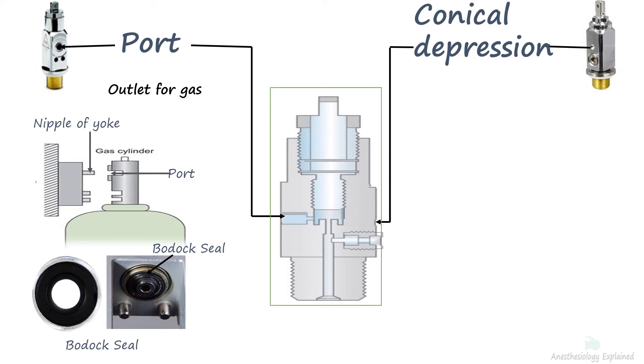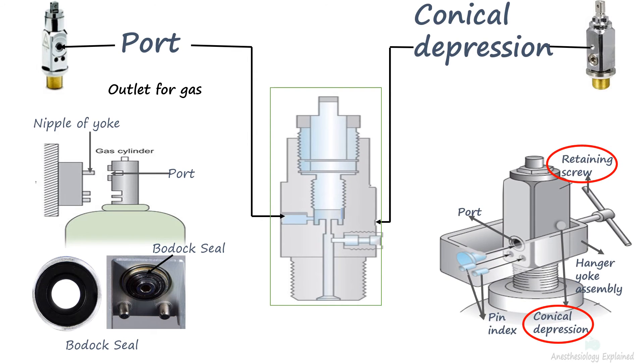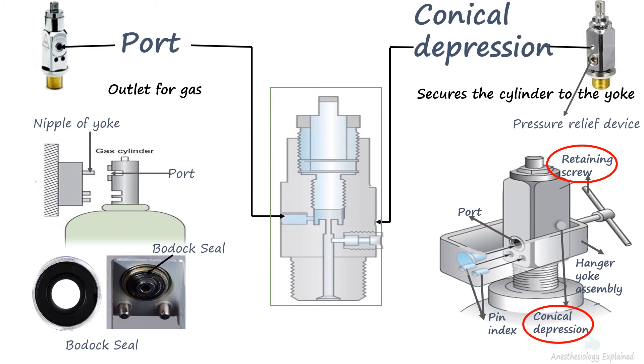The conical depression is situated on the opposite side of the port and is positioned above the pressure relief device. It is present only on cylinders designed for the anesthesia machine, as it fits into the retaining screw of the hanger yoke. It must be distinguished from the pressure relief device, as attaching the screw to the pressure relief device can damage it.